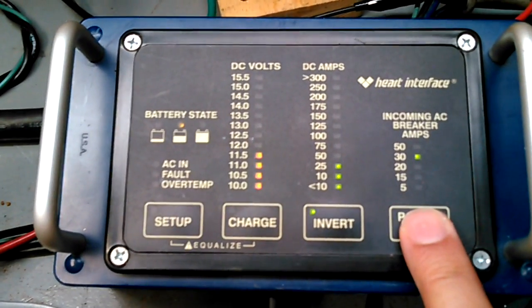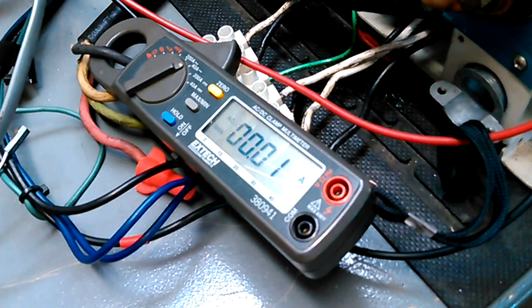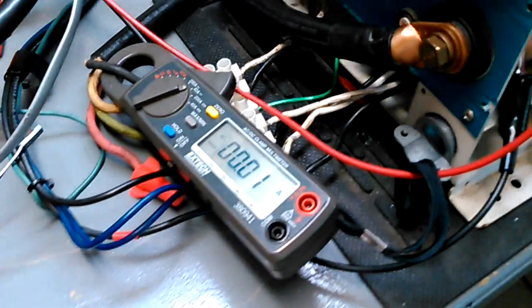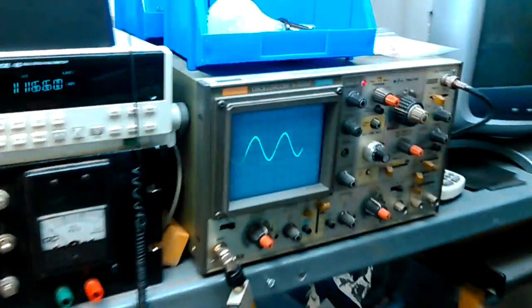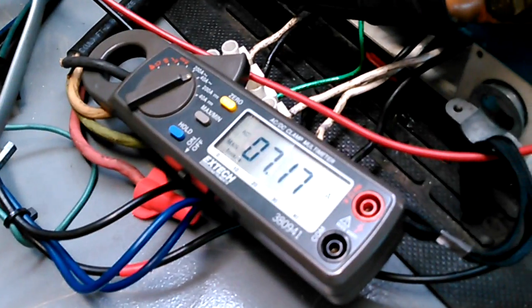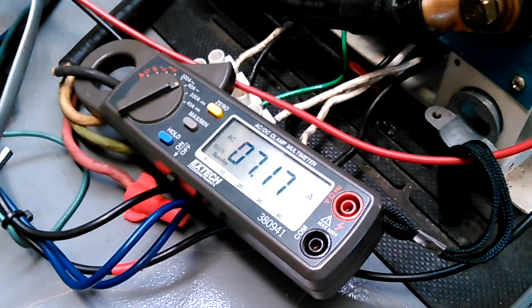But let me tell you why you may want to set it even lower. Right now, we're inverting. I've got a 1,000 watt load set. Well, no, I don't. Here, another 500 watts here. Okay, now we have a 1,000 watt load, and we're pulling 83 amps out of the batteries. Since we're running on inverter, we have no current coming from our shore power. I'm going to go ahead and switch on the shore power, and the inverter will switch to drive that shore power straight into my load. So my load is drawing 7.17 amps for my 1,000 watts.